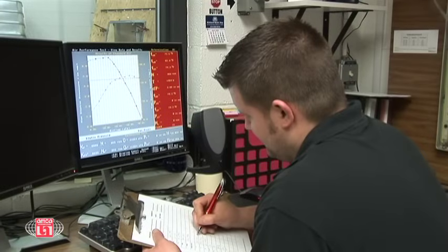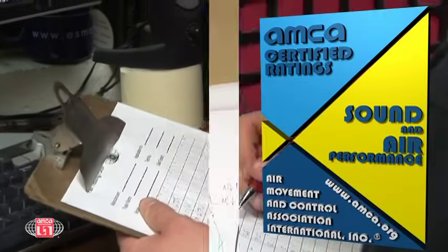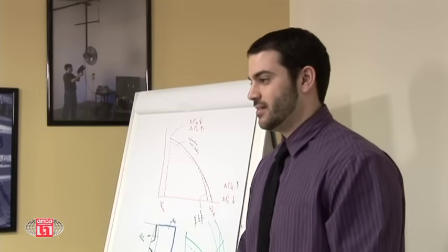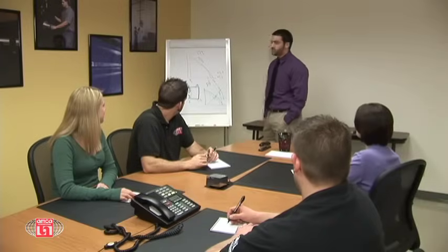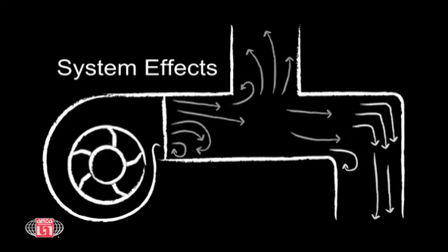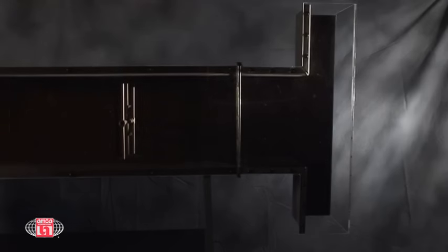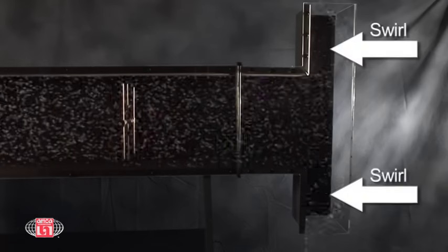Major elements of AMCA International are the Certified Ratings Program, Research and Testing, and education about HVAC equipment selection and installation, including system effects and its causes. System effects can be described as fan performance loss, the detrimental effect on fan air performance due to adverse flow conditions at both the fan inlet and the fan outlet.